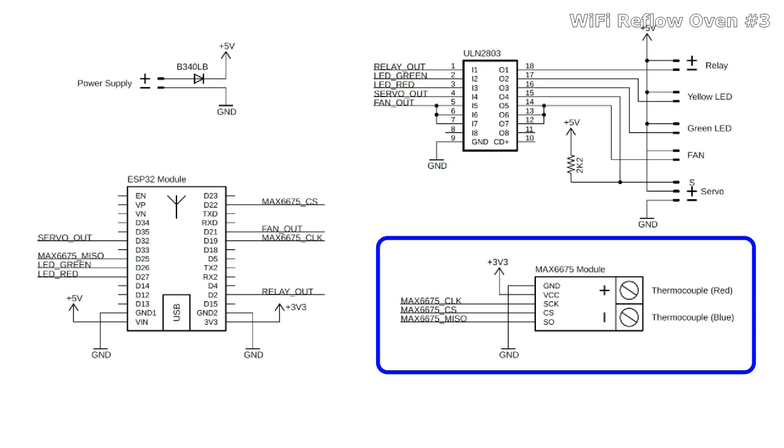In order to measure the relatively high temperatures of the oven, a thermocouple type K has been used. The thermocouple, based on the thermoelectric effect, generates a voltage proportional to the temperature, but this figure depends also on the temperature of the other side of the probe, the cold side. Fortunately, there are chips that already make the so-called cold junction compensation.